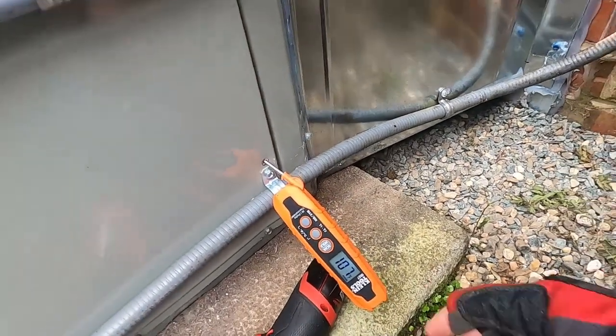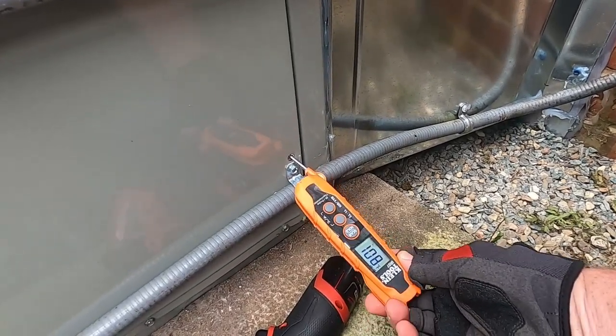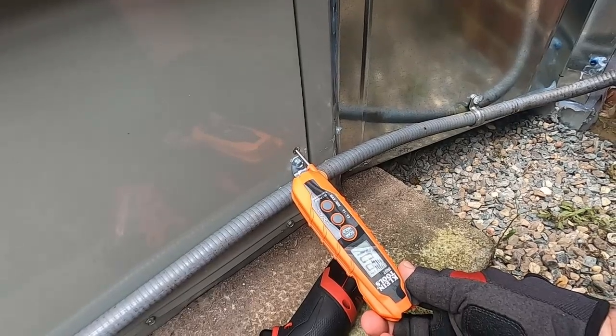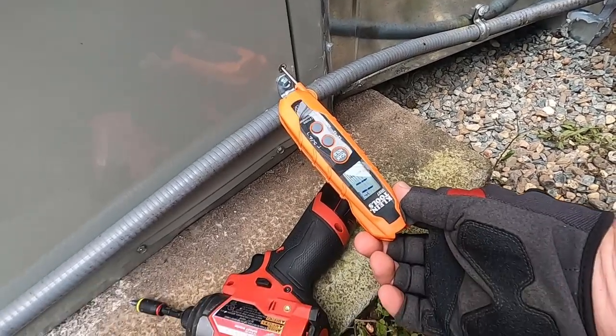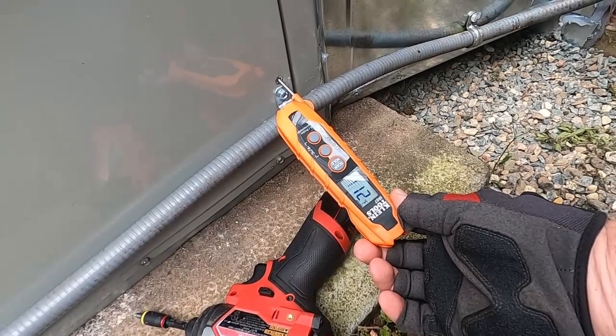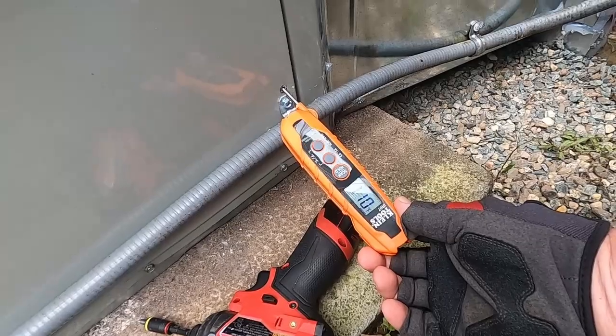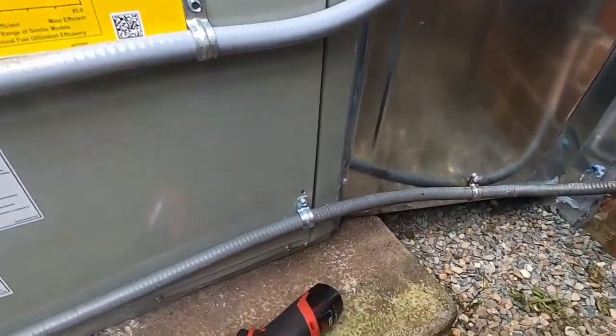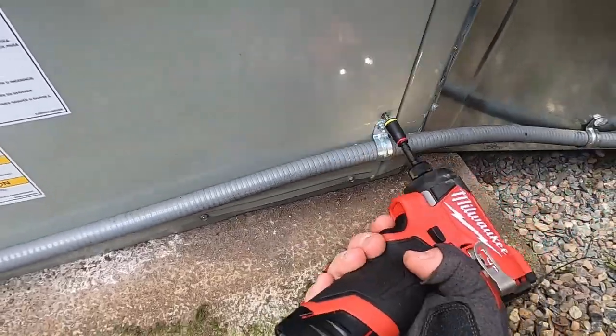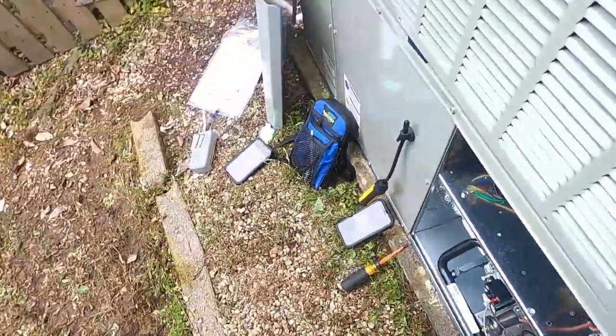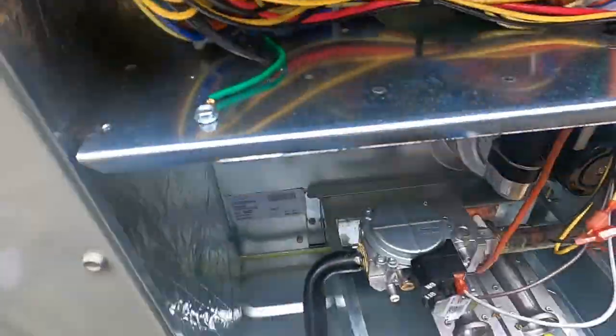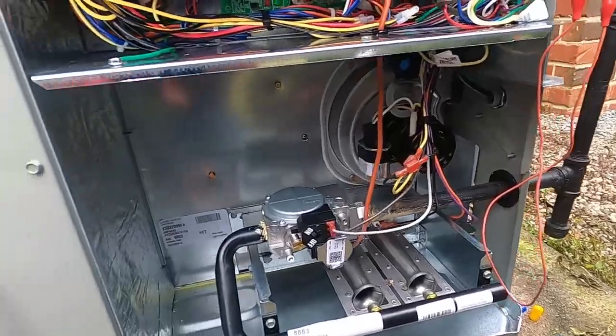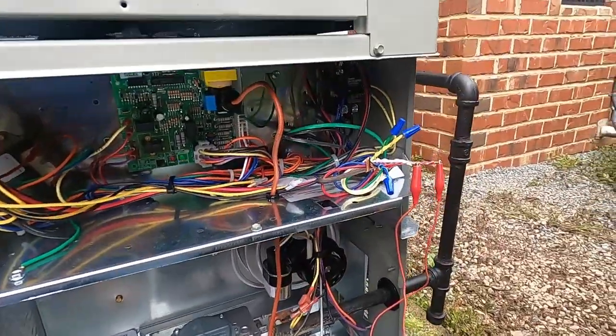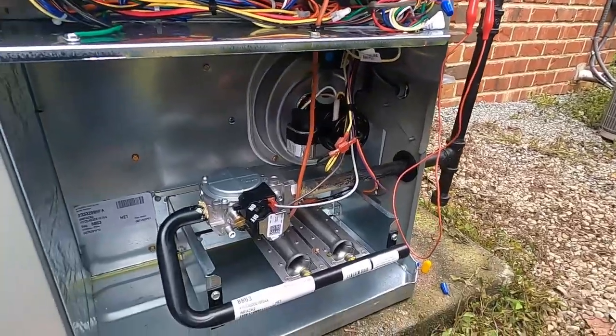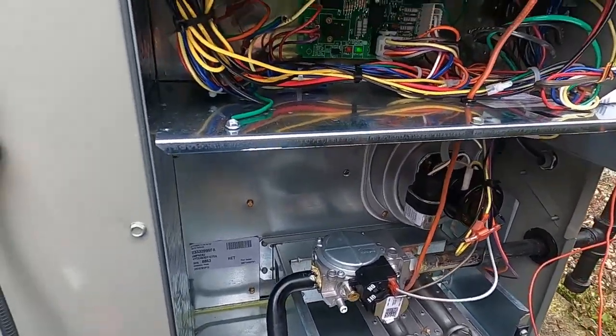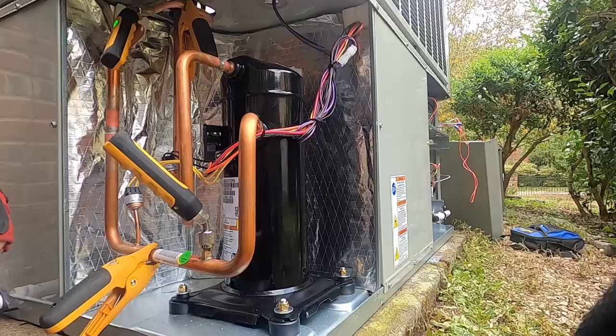And we're at 42, 40, almost at 45. So we are 46, 47. So we're going to be right in the middle, about a 47, 48 degree rise. So we are good on that. I don't have to get any amp draws on that paperwork, but I'm going to let the heat run just a couple more minutes, and then we're going to run this thing in air conditioning and get all those numbers, and that'll be it.